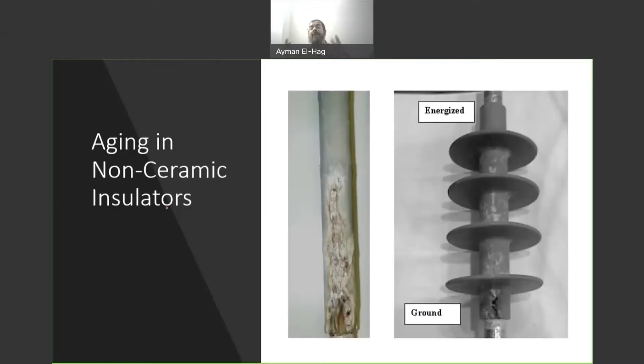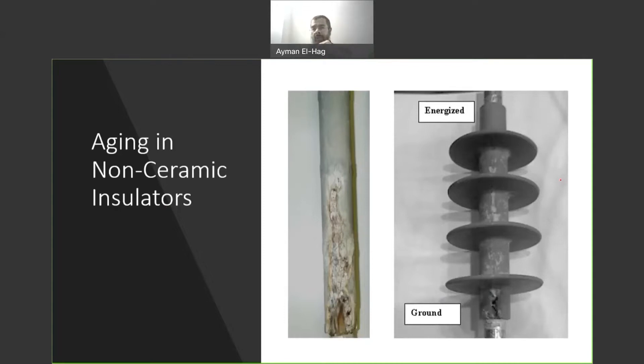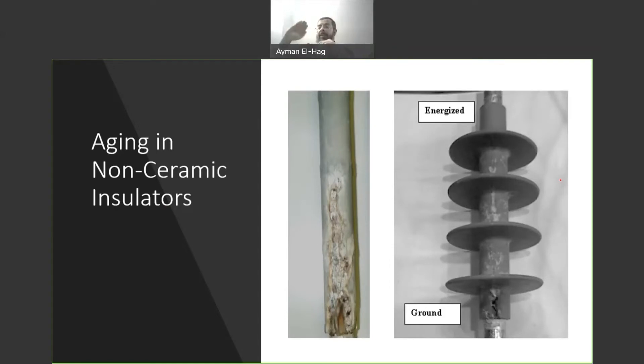Let's start with why we need to have an erosion test for non-ceramic materials specifically. Our outdoor insulators have to work under severe environmental conditions that include humidity, wetting, and high voltage — the applied high voltage and pollution. With this combination of high voltage, wetting agent, and pollutant, we start to have dry band arcing on the surface. Dry band arcing will lead to damage on the insulator surface. This is a 15 kV insulator and you can see some damages — erosion happening on the surface due to dry band arcing.